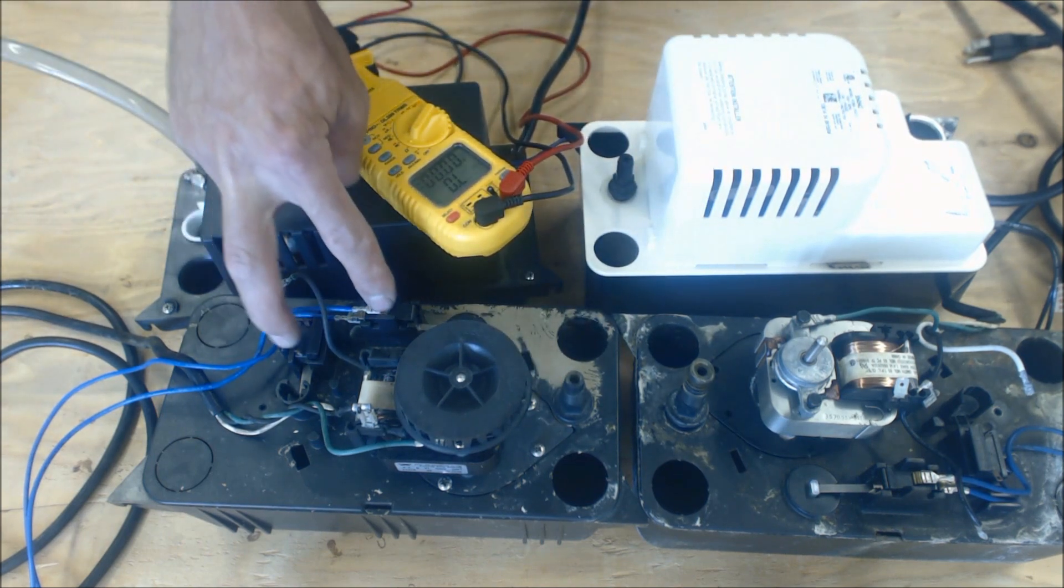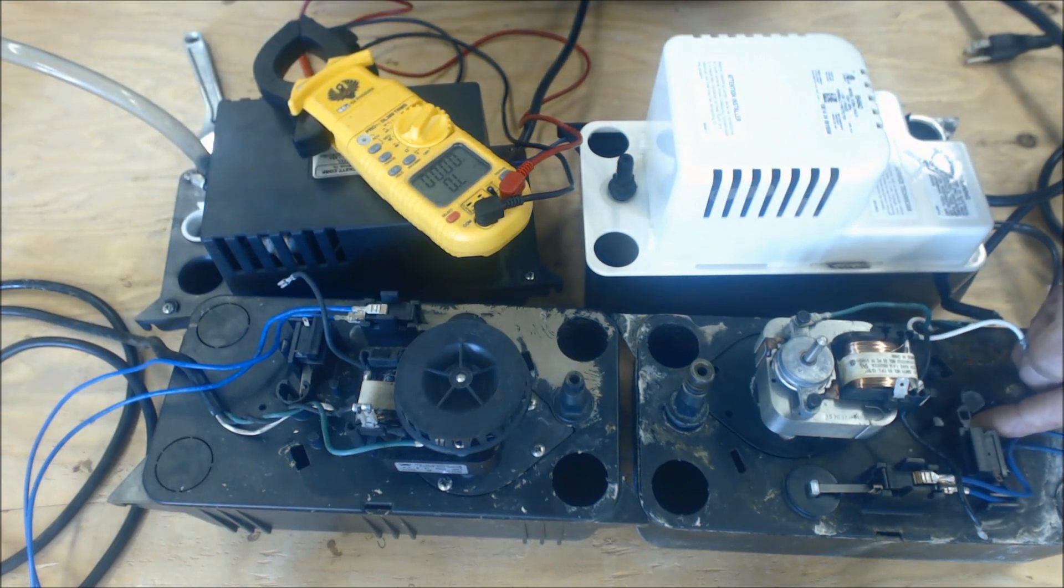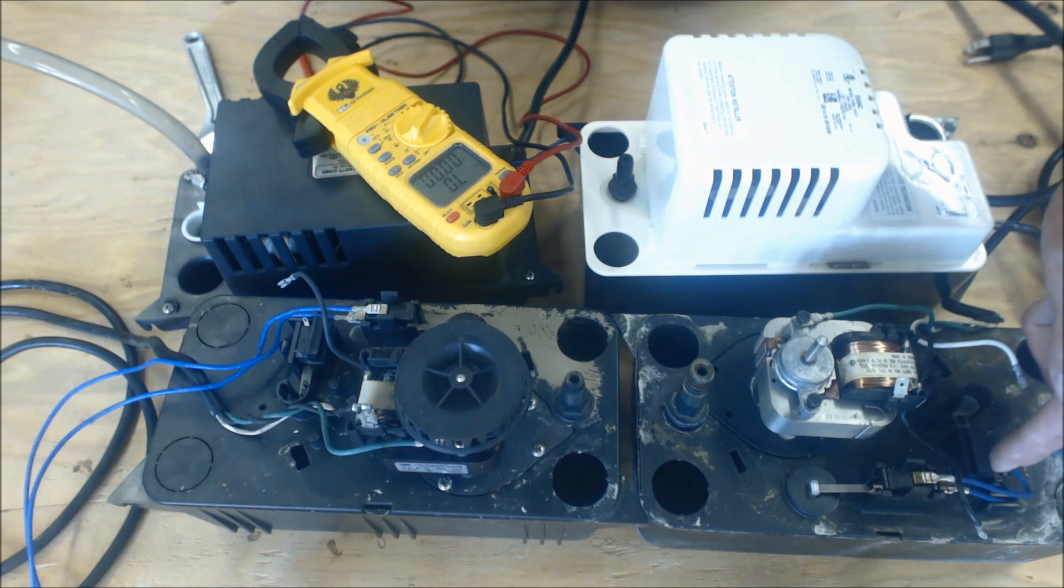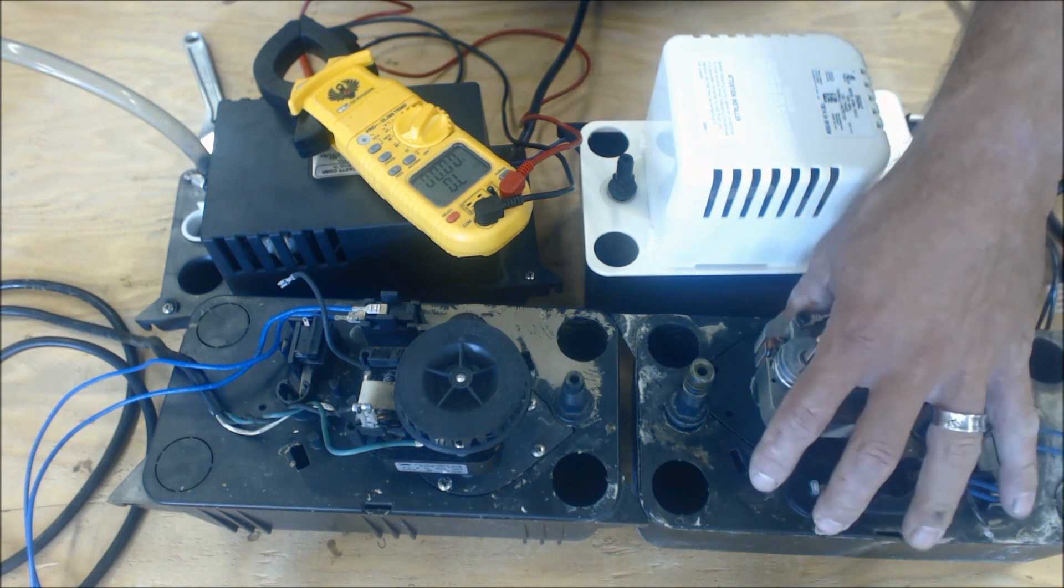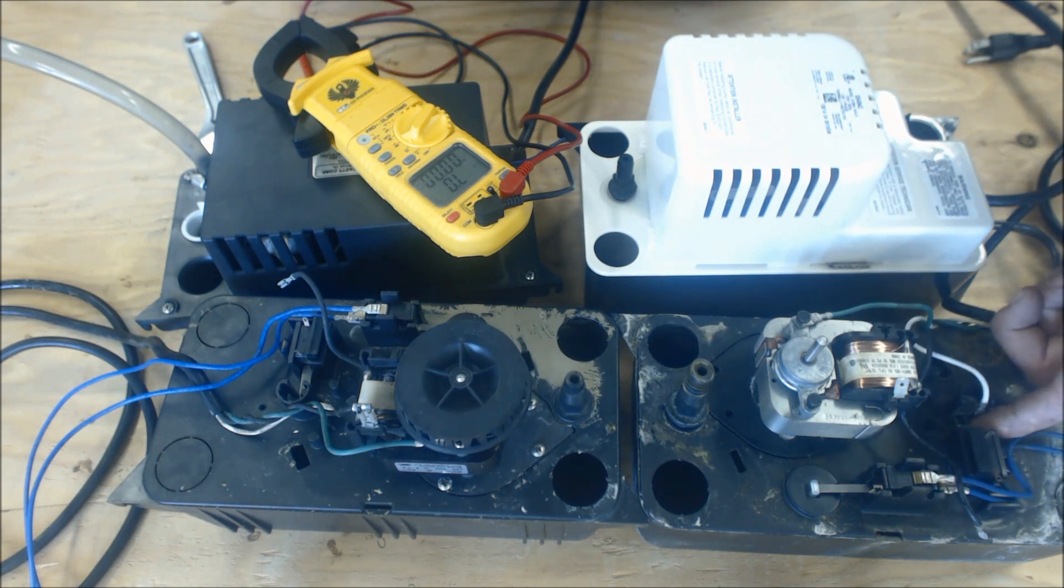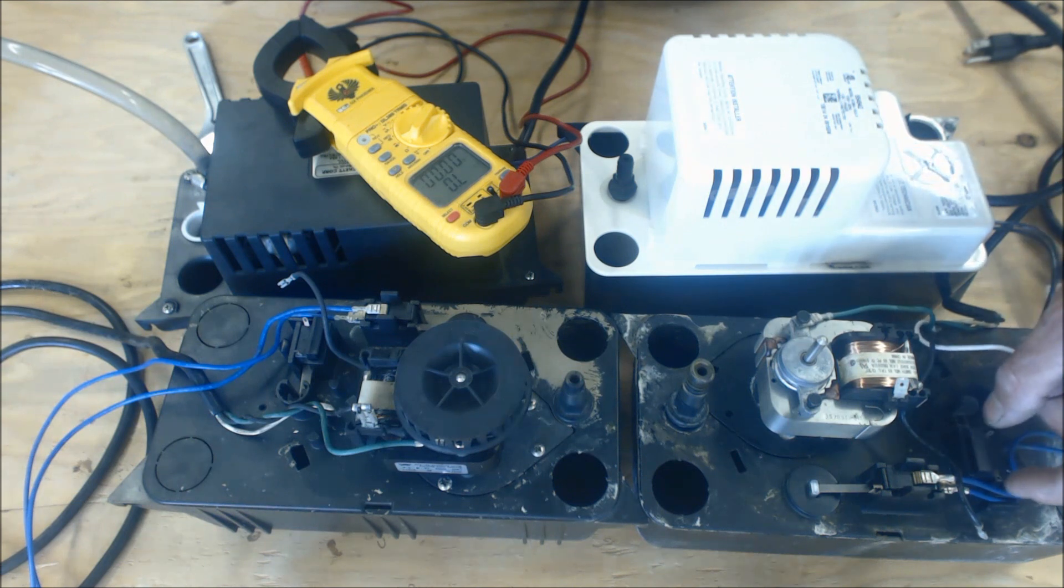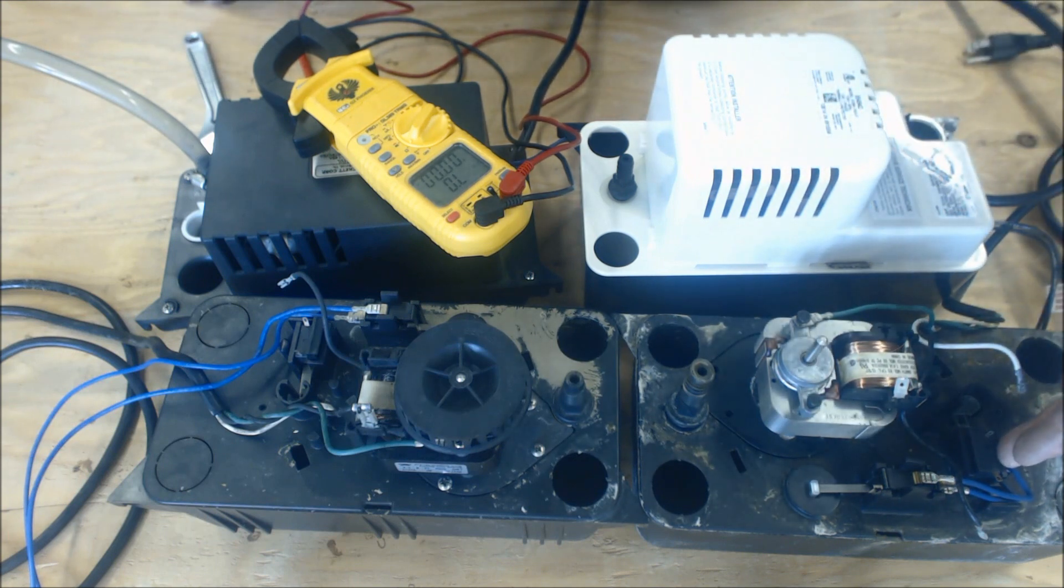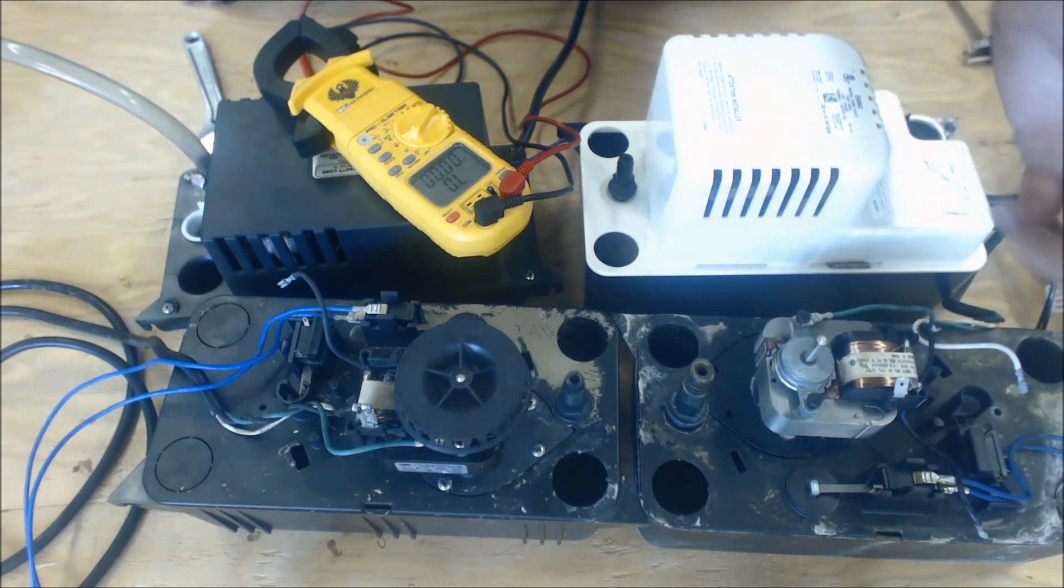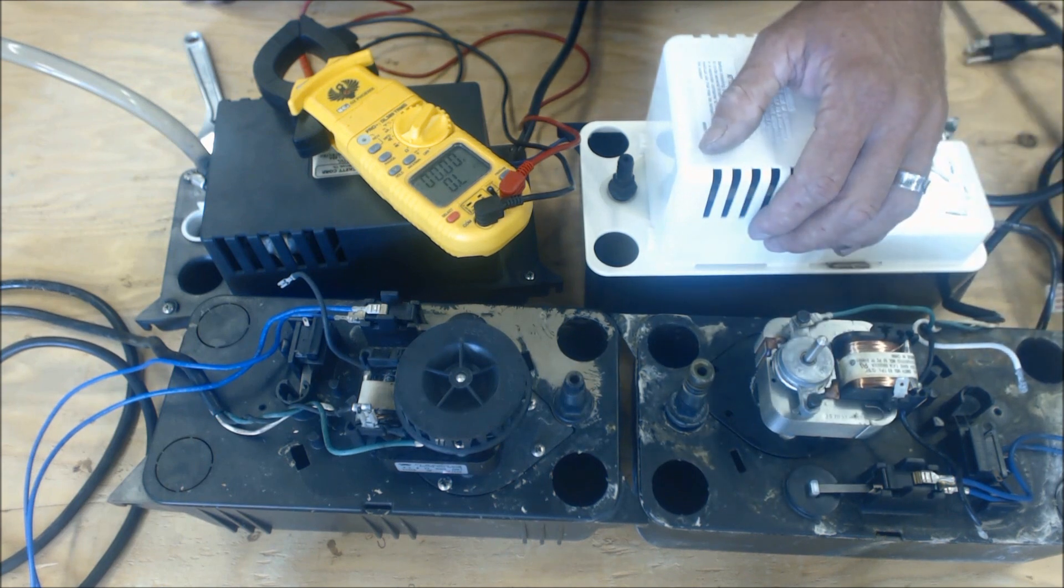So sometimes the micro switches fail. On this one right here, the micro switch is working okay now. I was actually just playing with it a little bit and it started making a good contact in here again. I don't know if that just had to do with the amperage running through here and it was just burning the contact or something like that in here. But this is now functioning correctly and that's why this one was pulled out of service, because that micro switch was not acting right. Now I don't know if that was due to the sludge that was not allowing this to come up all the way, or it was the contacts inside this. But for whatever reason it was not allowing the power to go through and the condensate pump was not turning on. And just to be safe, or safe and sorry, I replaced that just for the cost of the condensate pump. It was not that bad.